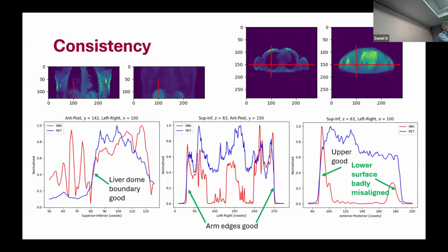Normally you fill the phantom with a saline solution in order to prevent MR artifacts. We didn't do that. We used pure water, and the Dixon sequence was a bit off. And the problem was that part of the patient table was also assigned as patient MUMAP.